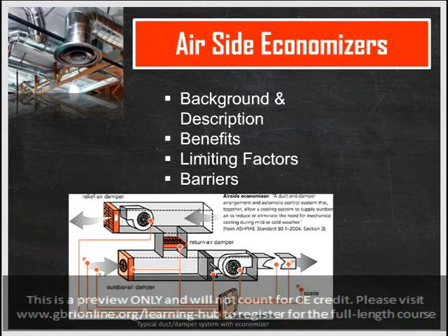Modulated economizer mode. During cool weather, between 30 degrees to 55 degrees Fahrenheit, for example, the required space temperature can be maintained without any mechanical cooling or heating by simply adjusting the mix of outdoor air and return air. In this mode, the economizer system adjusts both the outdoor and return air dampers, modulating these airflows to match cooling capacity with cooling load, without mechanical cooling. Intake airflow varies between the minimum setting and a maximum value to maintain the supply air or space temperature at set point.